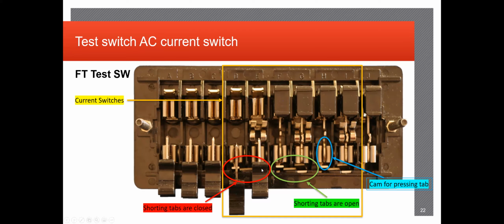So sometimes one of the tricks you can do when you're doing wiring checks on these circuits is put a credit card or some piece of paper in between them to break the circuit. That way you're not just beeping it out all the way through and not really identifying if the circuit's laid out per design intent. So obviously you want to remove the break in the circuit prior to energizing it in any way, shape, or form, but it's just something to keep in mind. And you can identify it with the shorting tabs, whether they're open or closed too.